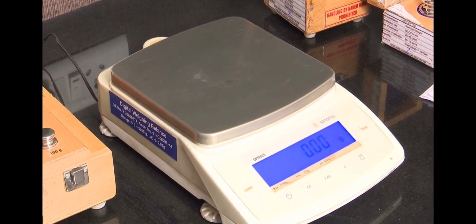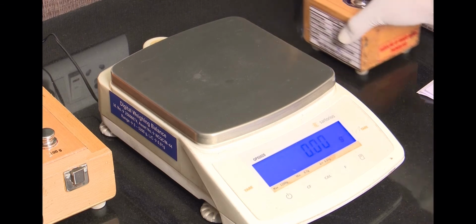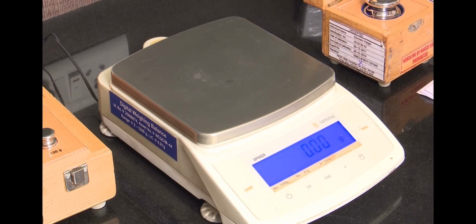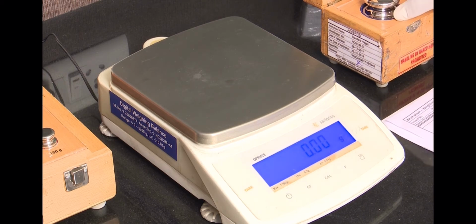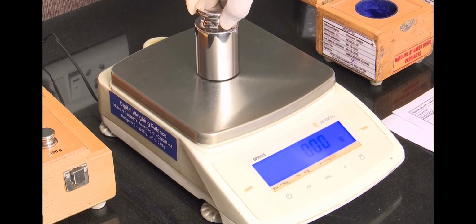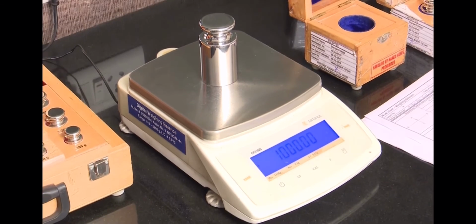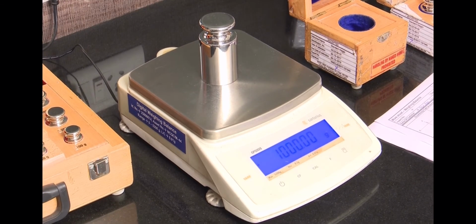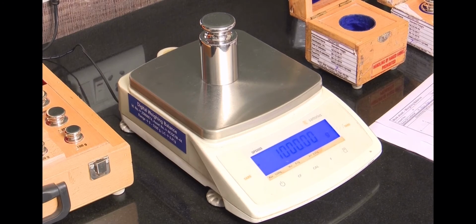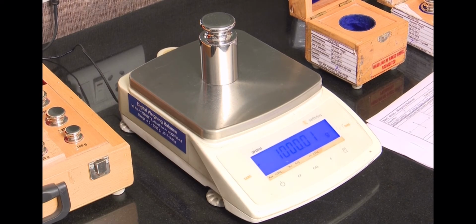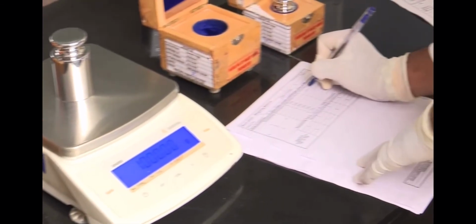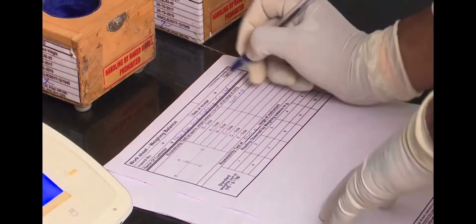Now I am performing eccentricity test. Select single reference standard weight nearly 1/4 to 1/3 of the range of balance. Here I have selected 1000 gram weight. Place reference standard weight exactly in the center of the pan of the balance. Take 1000 gram reference weight and place it on the center of the pan of balance. Now wait for stabilizing. Note down the reading shown by the balance for the reference standard weight that is on the center of the pan.